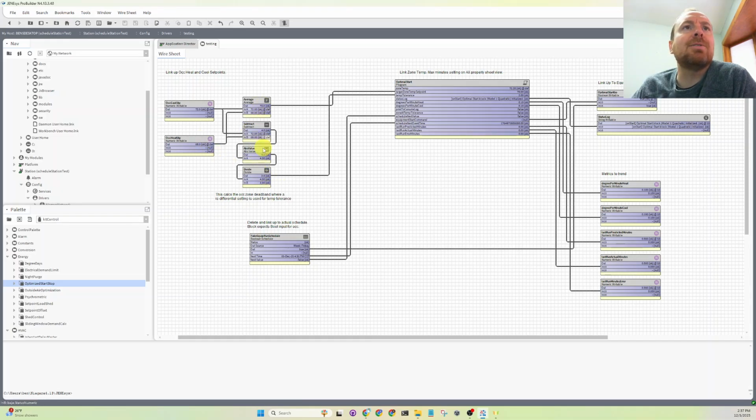And this is a little bit of code right here that's actually calculating that. And then in this block, there's a critical parameter called a temp tolerance that's just like a deadband. The way that it works is we'll monitor the zone temperature, and if the next equipment value is true, and there's a next time, we're continuously calculating how long it will take to recover that zone back to set point.